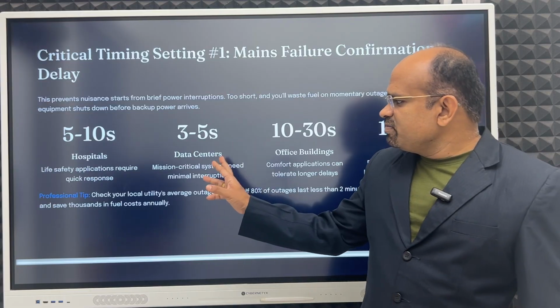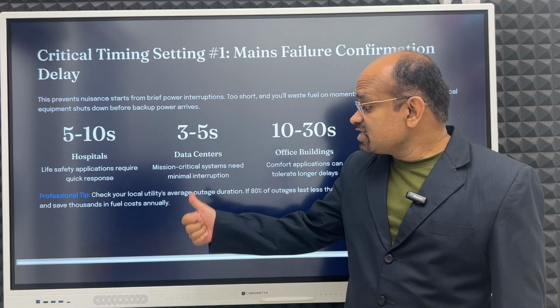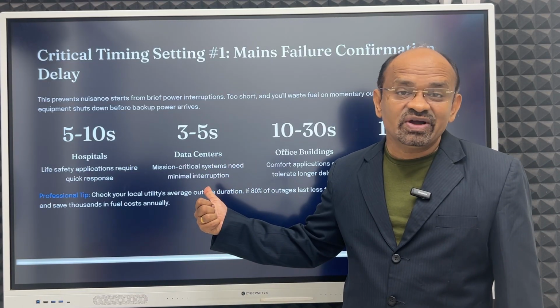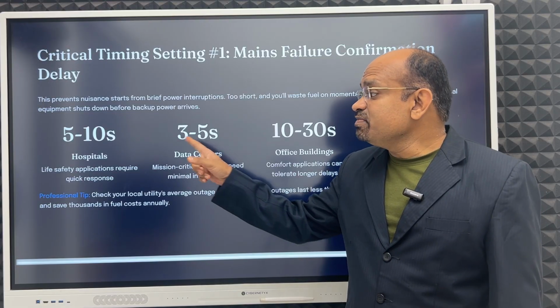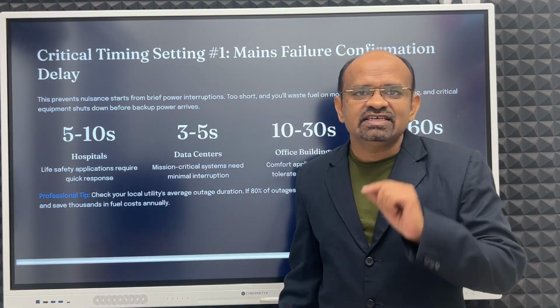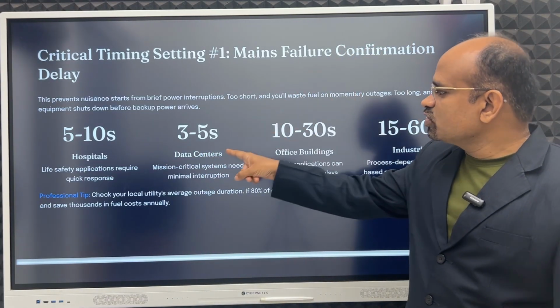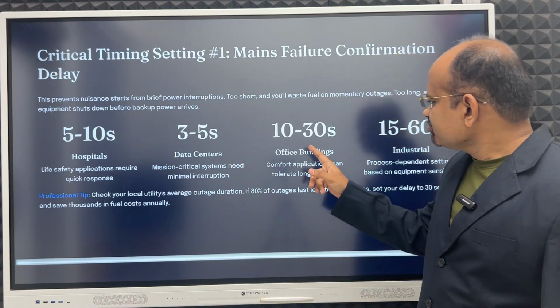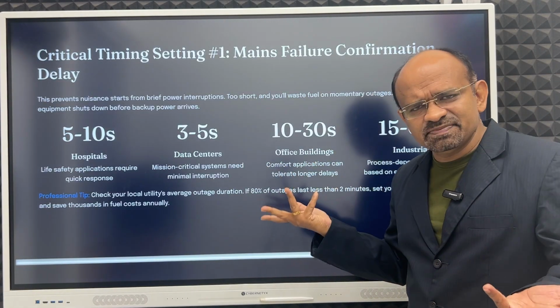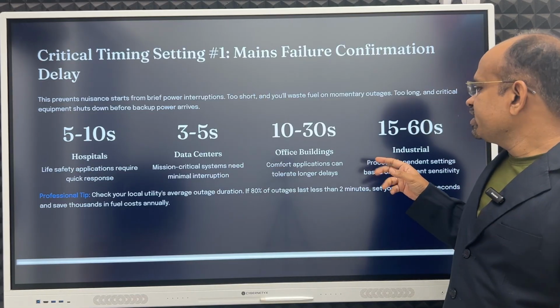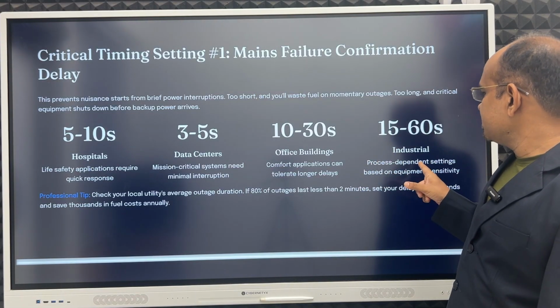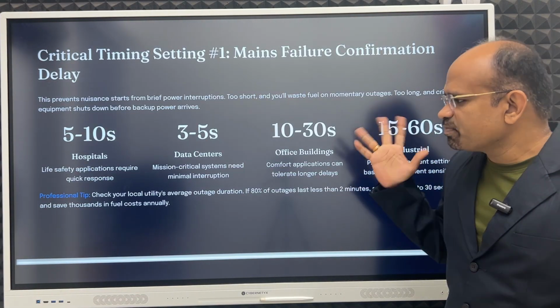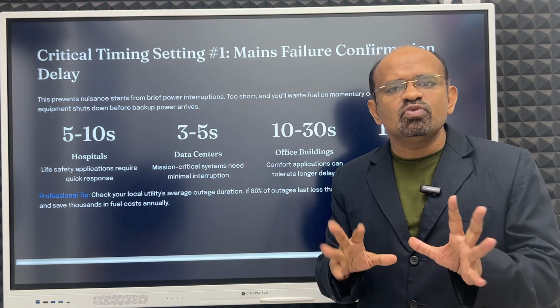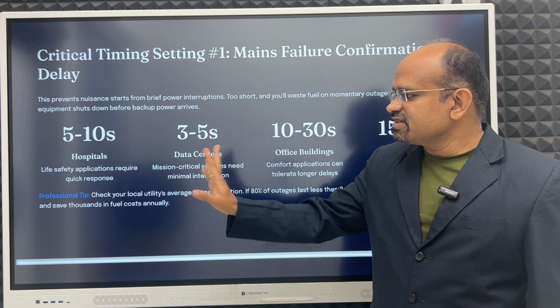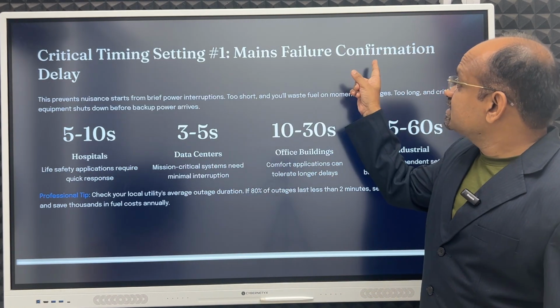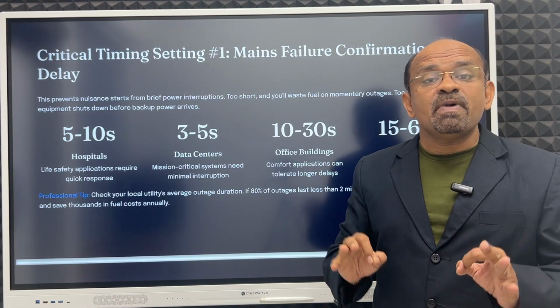Then 3 to 5 seconds for data centers. So these are mission critical loads. So for that, 3 to 5 milliseconds, very critical. That is why less time. For the confirmation, it should confirm quickly. Then 10 to 30 seconds for office buildings, normal load, not to worry. Then 15 to 60 seconds for industrial processes. It can take a little more time, but these mission critical things should assess and confirm there is a power problem in the input.